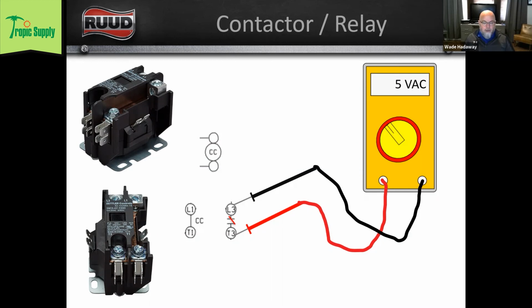I know that the National Electric Code tells you that you shouldn't allow for any voltage drop more than 5%. What's going to happen though is if you're out there and you see that you've got a 5-volt drop, when you leave, that pitting or whatever's causing your voltage drop across that contactor or across that set of contacts is just going to continue to get worse. So on a good switch, you shouldn't really read any, maybe fractions of a volt. But as a best case scenario, if you've got contactors that have a drop across the contacts, you should replace them, or relays.